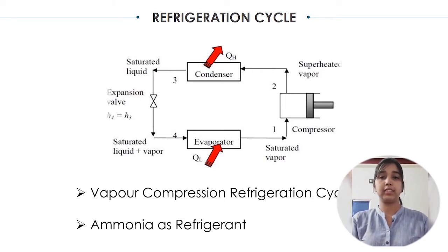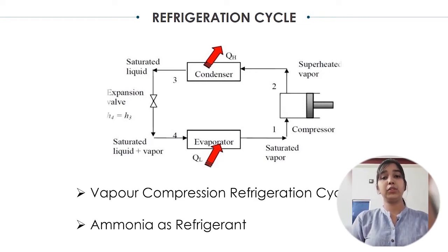the same process. Here we are using a two-stage compressor, as staging of the compressor will result in a reduction in work done to compress the vapor, and it will also prevent mechanical problems, as a mechanical problem will be faced when a single stage compressor is used, because there the temperature of the refrigerant will be high. Now here we are using ammonia as the refrigerant.